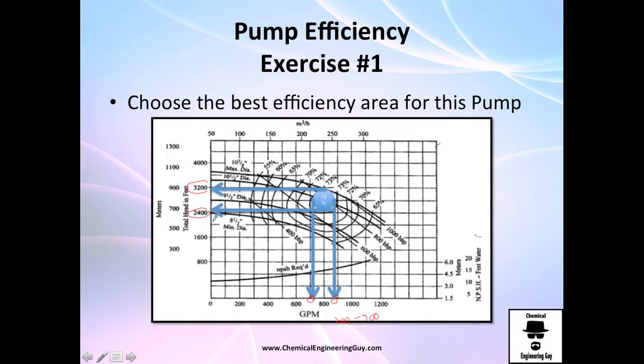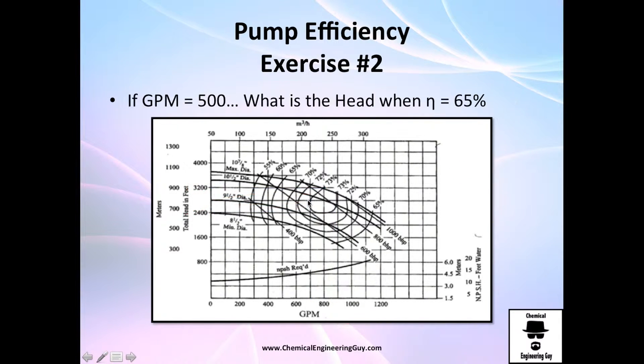It will be delivering a head of between 2,500 and 3,000. So if our system happens to be, say, 800 gallons per minute and we need a head of maybe 2,700, this pump will actually be very good for the task.